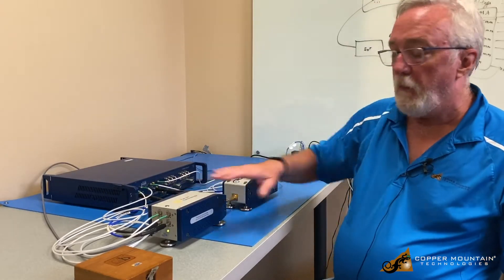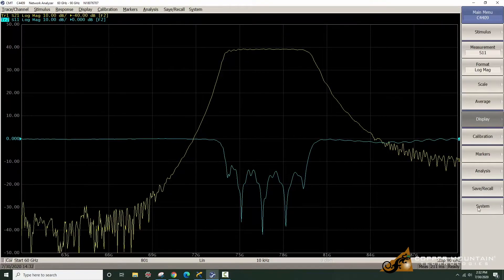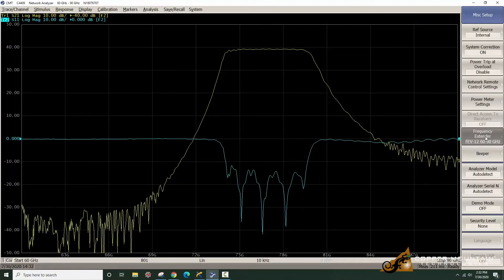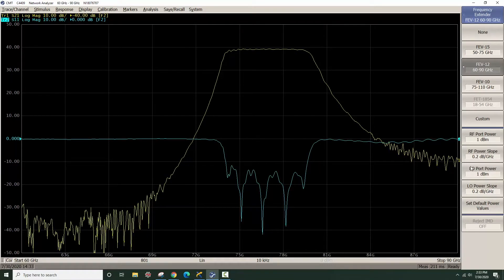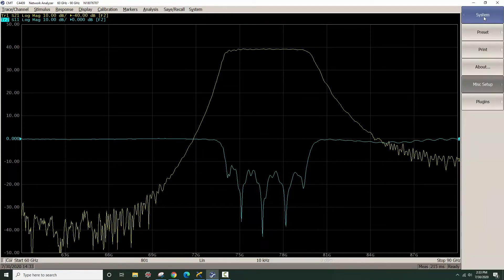First I had to set this up in the software. If one goes to System, Miscellaneous Setup, Frequency Extender, I chose the FEV-12 system, and the settings for the RF power and the LO power were all set here. Then once this has been set, you can see that the bottom of the screen extends now from 60 gigahertz to 90 gigahertz, and we're ready to make measurements.